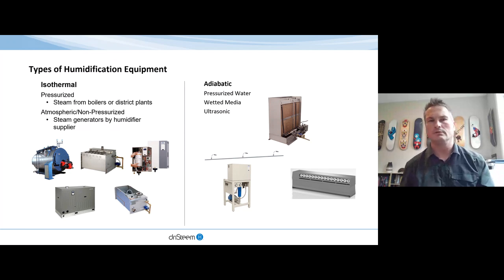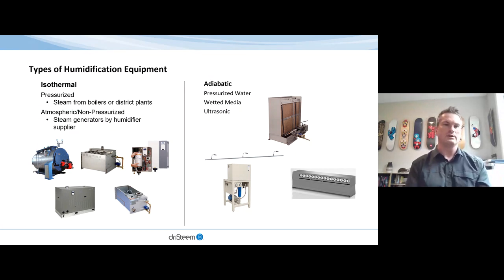So what do these types of equipment look like? Well, isothermal equipment includes steam generators and steam boilers, through direct district plants or localized steam pressurized boilers, or atmospheric non-pressurized steam generators, where the water boiling is atmospheric, meaning just like the pot of water on your stove, that steam is atmospheric. It doesn't have extra energy pushing it through. It's not contained within a closed network or system. So it has the liberty of being transferred through its steam line at an atmospheric level. Adiabatic technologies, again, are the wetted media, the high pressure nozzle systems, and the ultrasonic systems as well.